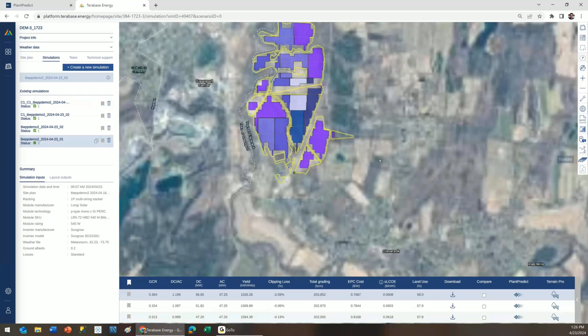The first simulation I ran used a very simple optimization, targeting 50 megawatts AC. You can see all of these come in at 47.25 megawatts AC. I increased the DC-AC ratio from 1.0 to 1.1 to 1.2. The way we were able to increase the DC associated with these scenarios is by increasing our ground coverage ratio, which went from 31% to 33% to 36%.